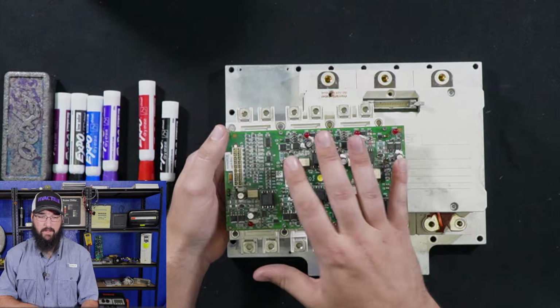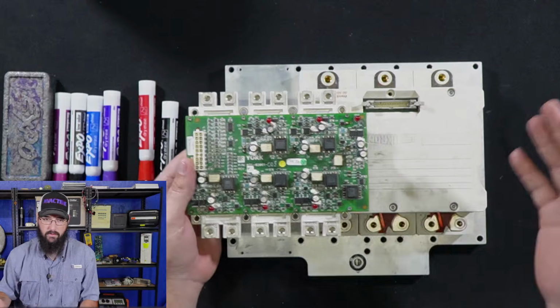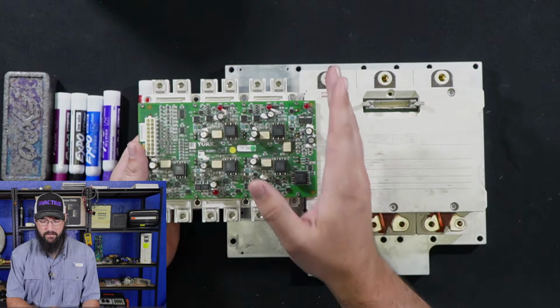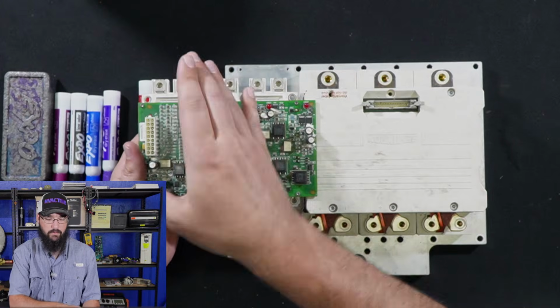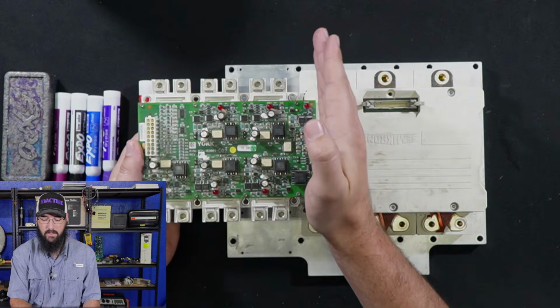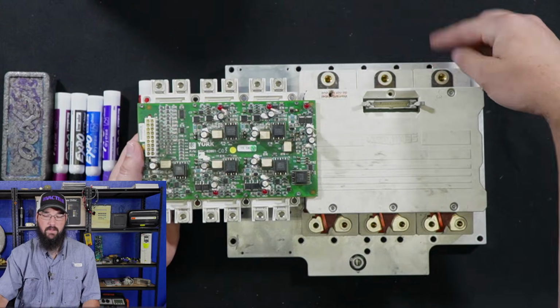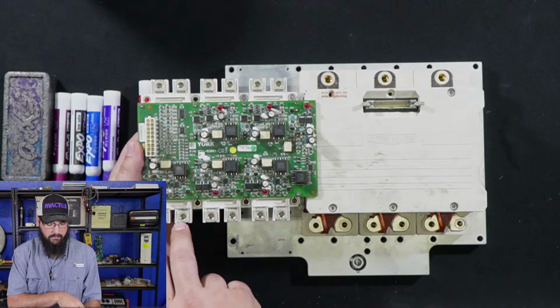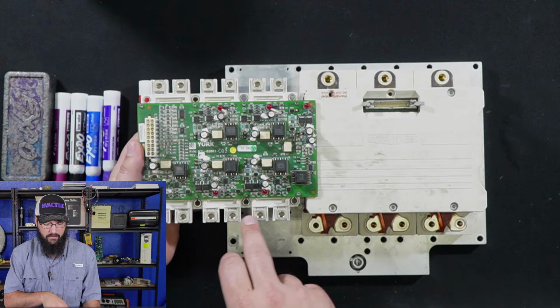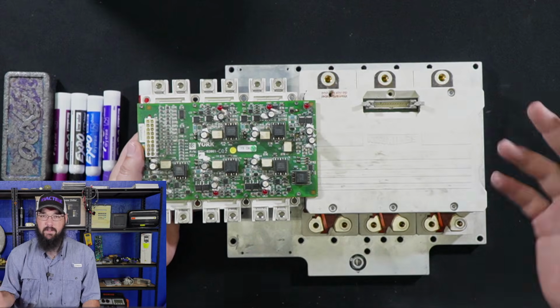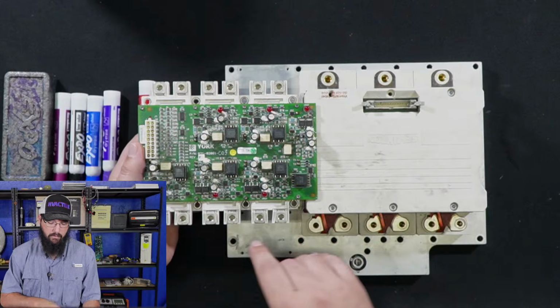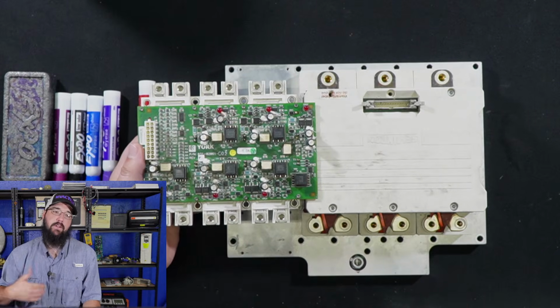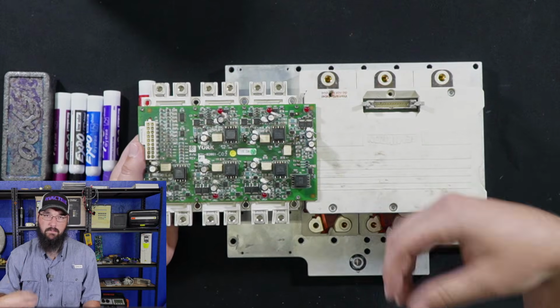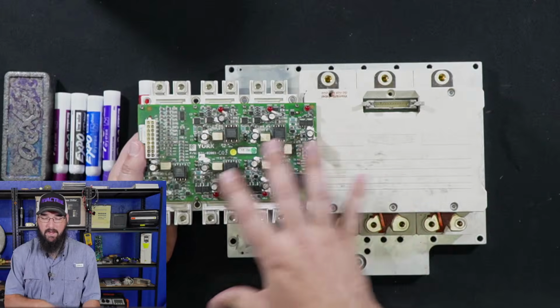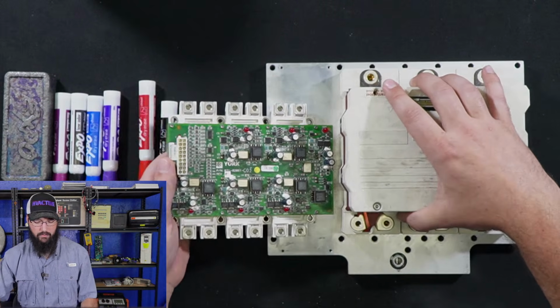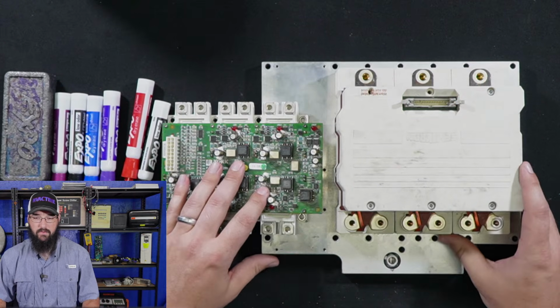This is what you would commonly see out of a York, Danfoss York. These are the exact same thing, even to the fact that this is one module unit and this is one module unit, but there are three individual sets of gates in here: 1, 2, 3, as you can see by the outputs. Technically these are the other way around. These are negative, positive, negative, positive, negative, positive, where this is positive, negative. That is not really all that relevant. The point is we have a two-point input from the DC bus. We're coming off a DC bus with a capacitor bank and all the things we would have on either of these drive assemblies. And we're going to notice that these two modules troubleshoot very much the same.